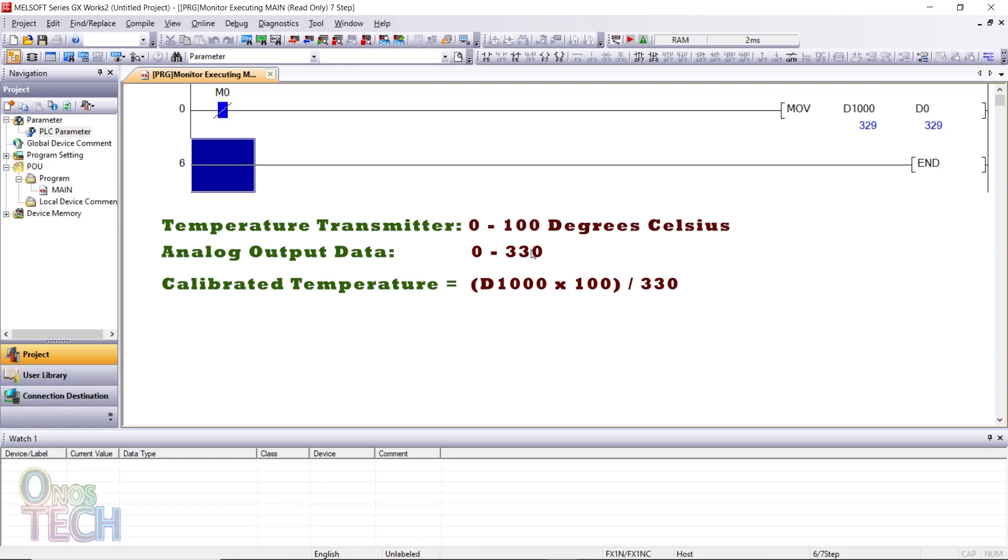The calculation to determine the calibrated value of the temperature transmitter is D1000 times 100 and the result is divided by 330. This can further be simplified to D1000 times 10 divided by 33.